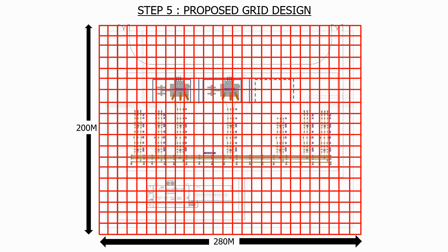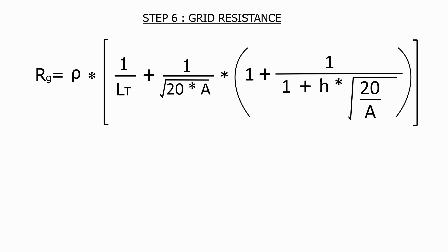Once we've decided on the spacing of the conductors, we can then start doing our grounding grid calculations to see if our initial design is safe. To start this process, we need to look at the grid resistance, which is obviously the resistance of the overall grounding grid that we bury in the ground. To calculate this, we have this standard formula which again contains many constants and grid parameters.